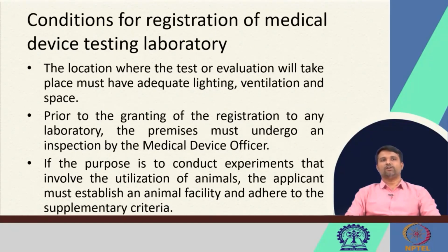Conditions for registration of a medical device testing laboratory are also provided in the 2017 rules. The location where the testing or the evaluation will take place must have adequate lighting, ventilation and space. Prior to the granting of the registration to any laboratory, the premises must undergo an inspection by a medical device officer. If the purpose is to conduct experiments that involve the use of animals, the applicant must establish an animal facility and adhere to the supplementary criteria.